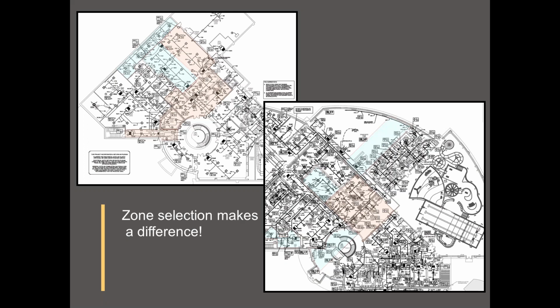The point I want to make is that in the design of this system, the designer made a specific effort to try and mix zones among the outdoor units, and I think they missed an opportunity, probably inadvertently, but you can see the light blue area, that's a zone or some indoor units connected to one outdoor unit. Similarly, these other blue zones are all connected to the same outdoor unit. And then the sort of pink color is yet another outdoor unit, and that same outdoor unit is also connected here in the upper level.